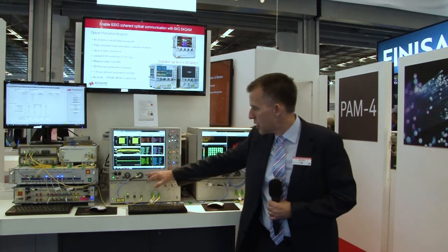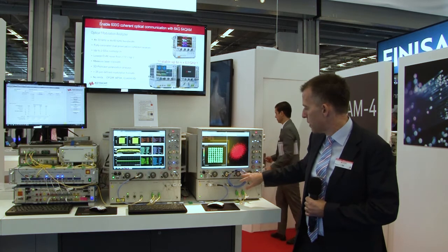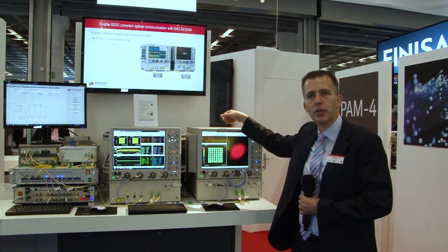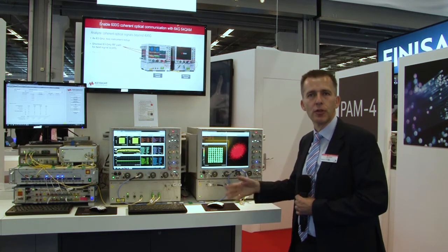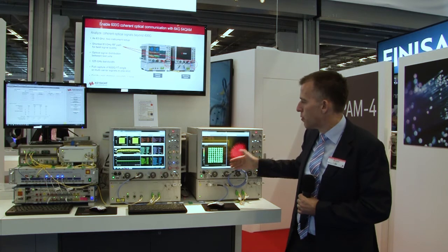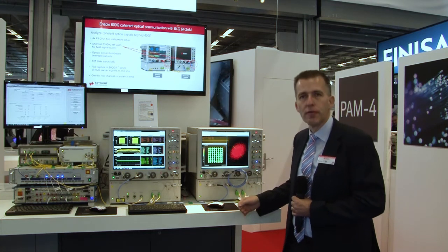There's some synchronization between the two instruments with these blue cables here. There is a LAN connection on the back and a trigger line. That's all we need to synchronize the two boxes to provide the analysis of optical signals.